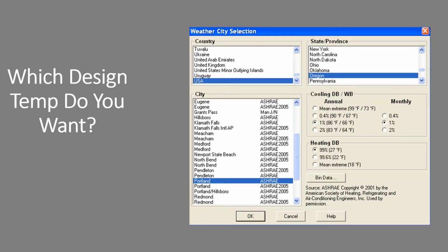Please notice that on the cooling design temperatures, they give you a few options. The 2%, that would be only 2% of the time does it get above 83 degrees. The 1% is 86. The 0.4 is 90. Well, summers are getting warmer and summers are getting smokier. The mean extreme is 99.